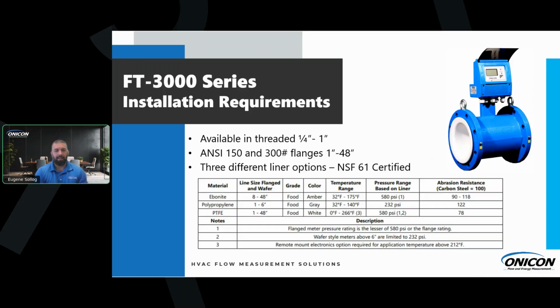With PTFE, that's what we're going to always use for heating hot water, domestic hot water, and any kind of chemical additives or abrasive additives. We're going to want that PTFE liner in that. That's to include brine or any kind of salt or seawater that might be coming in.